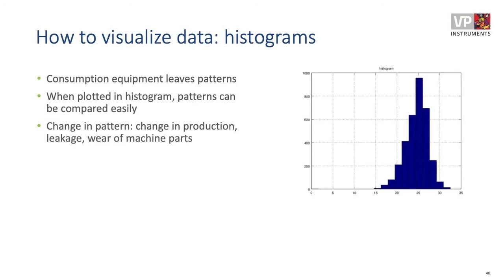But actually, there were very many leaks when we started to investigate. There was a lot of inappropriate use of compressed air. We changed from agitation in vessels from compressed air to high pressure blowers instead, just to give you one example. They started a leak maintenance program.